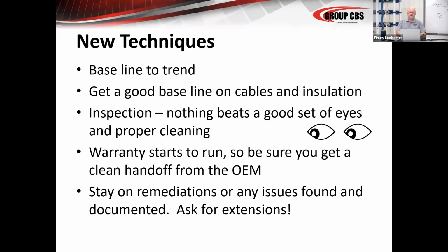But the thing you have to realize is what that warranty actually is, because once it starts to run, it starts to run. And once the warranty starts to run, you need to make sure that the manufacturer has done everything that you've found. So let's say you have found 30 or 40 discrepancies in the switchgear. There's 2 or 3 instruments missing, not uncommon. The wires are running through the empty holes. There's a tag on it that says this is being shipped to you. It was back ordered. That happens quite often with new gear because they believe it will get delivered, and they'll have their outside service team come and install that device before you get to startup.